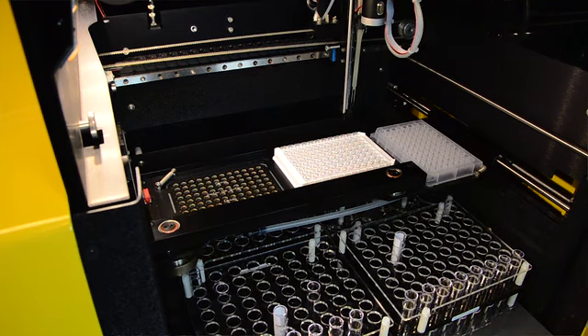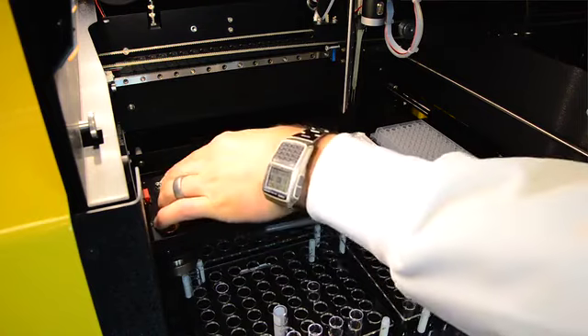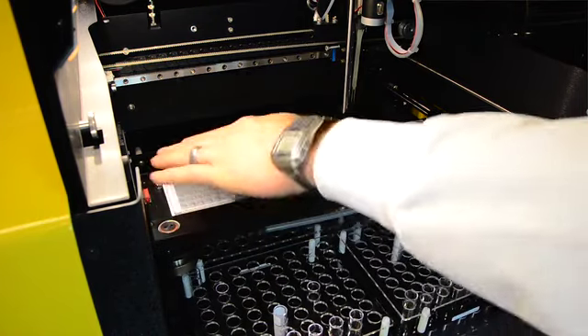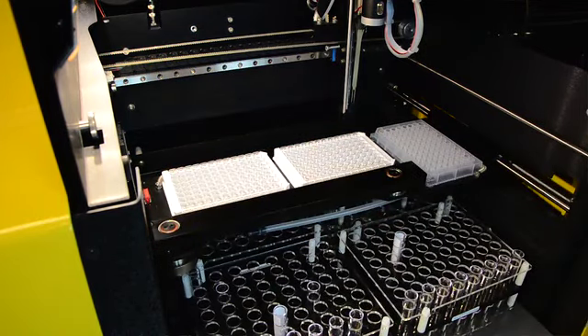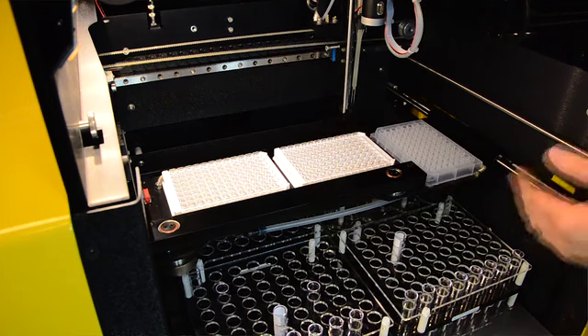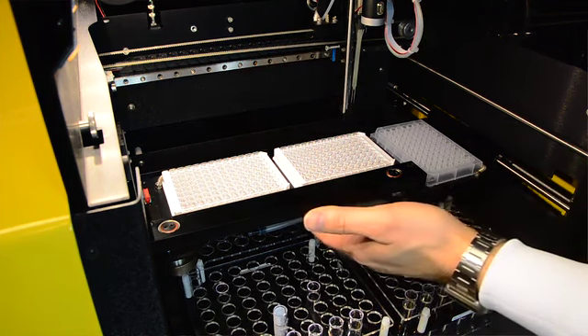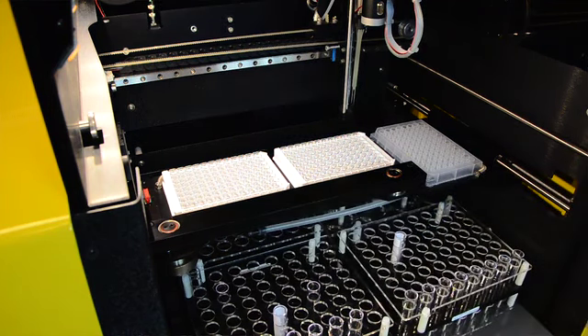On a 96 well plate format test, the outer wells are exposed to more of the atmosphere within the chamber than the inner wells. On our system, every single well is heated by the same number of resistors beneath it. So across the whole plate, you will get an even distribution of heat. We also have air that is being blown through a pump here that comes up through the resistors and allows the air underneath to be homogeneous.